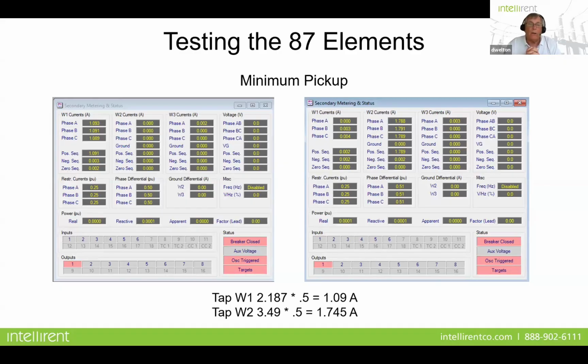Okay, so what do we do next to test the element? Well, the next thing is we're going to check the minimum pickup. And remember, our minimum pickup setting was 0.5. Now that's not 0.5 amps. That's 0.5 per unit of differential. So what that means is if tap winding 1 is at 2.187 amps times 0.5, our minimum pickup should be 1.09 amps. So we're going to put the secondary windings at 0 and just ramp up our current until the relay trips, and that's exactly what it should trip at. Okay, that's the minimum pickup.